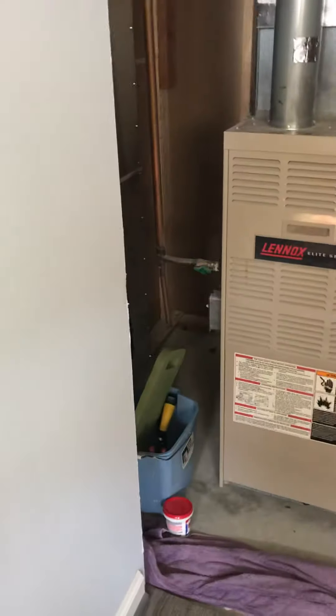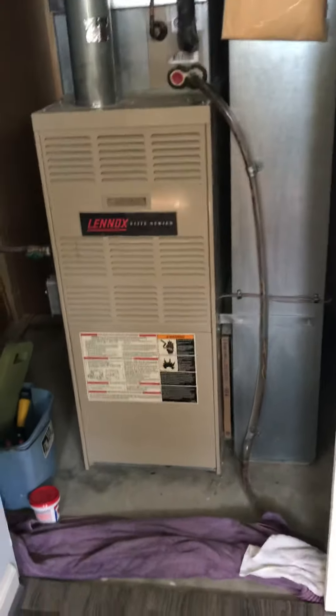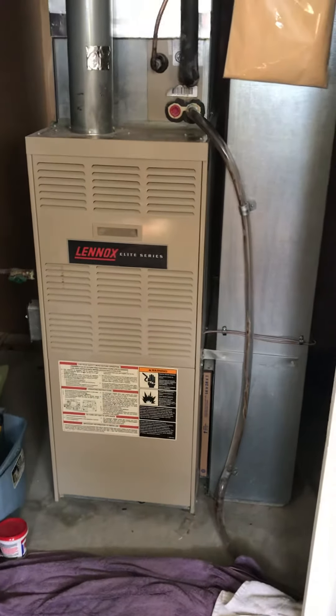As I was mentioning, there's some space on that left side. There's the option for us to get a wider filter in here if we just do an offset to make room for the 7-inch wide media filter. There'll be plenty of room to slide that in and out in the future.